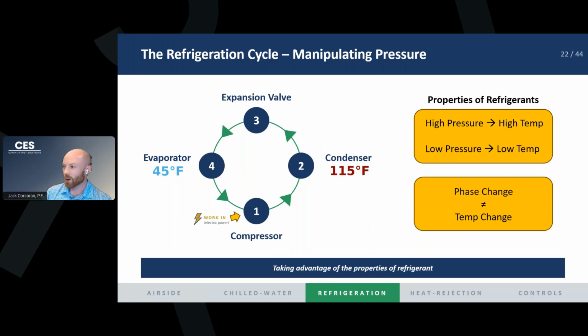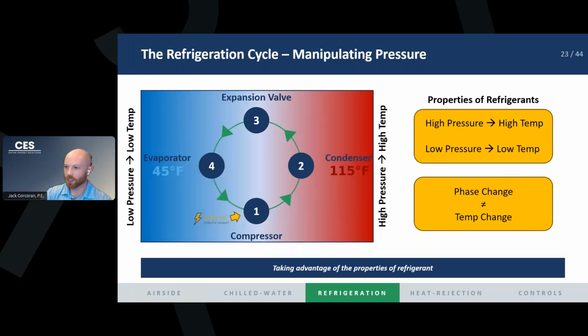But really, what are we doing here? We're manipulating the pressure in order to get those temperatures. Remember, we have to add in work. This is where all of our energy consumption is, at our compressor. We are pressurizing our refrigerant, making it high temp, high pressure on the right side, and then we are using our expansion valve to reduce that pressure and make it low temperature refrigerant to send back to our indoor DX cooling coil. We talked about this last week in VRF fundamentals a little bit more, if you want to go back to that presentation. But essentially, we're making a hot and a low temperature side, and we're just manipulating pressures to do that.